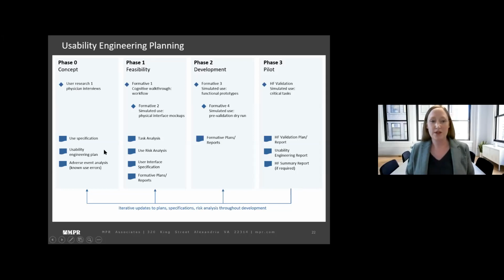All of that can be used to develop a high-level usability engineering plan for the program. That is the plan for the set of activities that will be completed within your strategy for the program. And then it's also typical in phase 0 to start thinking about known use errors, completing adverse event searches, such as through the MAUDE database or information that you might have on similar devices through post-market data. So we usually start trying to look at that as an input to the use risk analysis as well in phase 0.